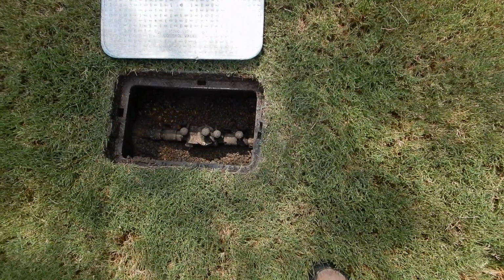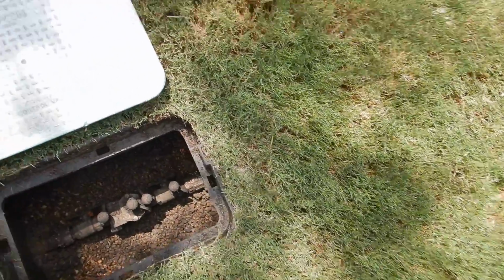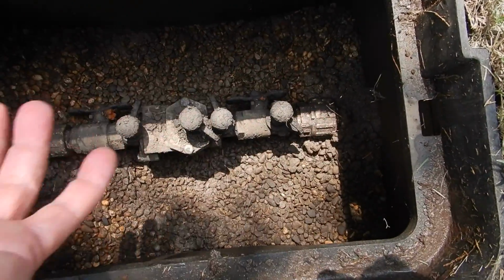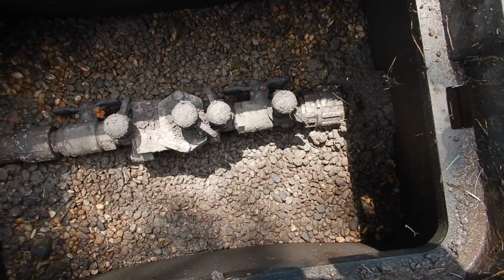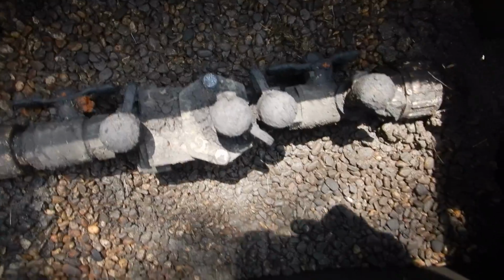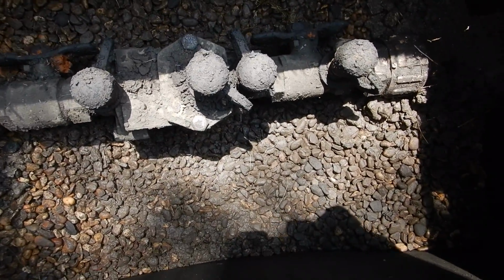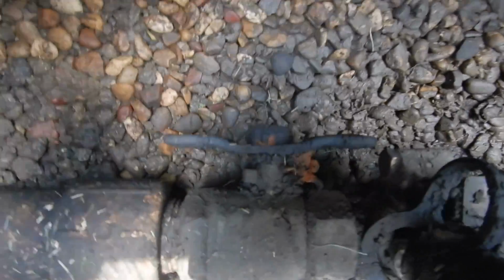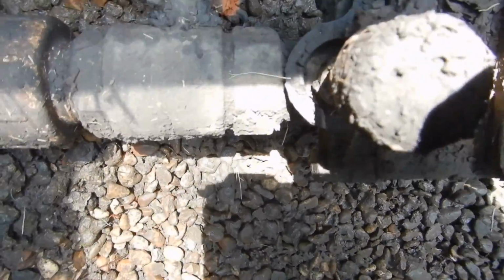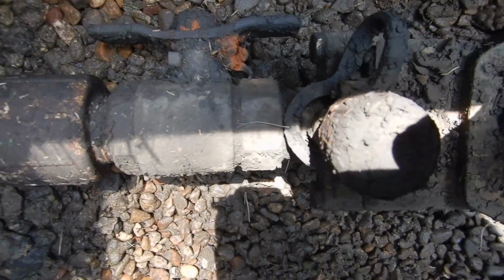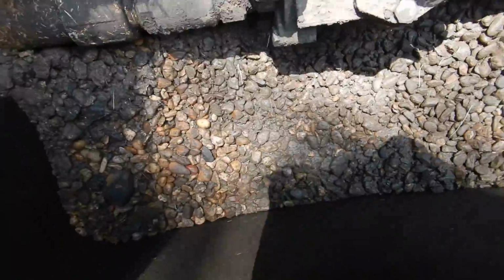Jump ahead just a moment. Okay, it's been lined with gravel, but you should have about 3 inches of clearance underneath that valve so somebody can get their hand around there and service it. Obviously, nobody's serviced it in a while. The handles are rusty. Is that going to break off if you try to turn it? I bet it will.